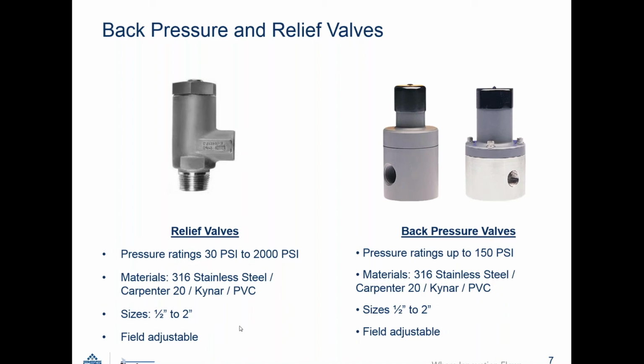Back pressure valves are required generally when there's a pumping situation where it's going into a low pressure situation. Pumps generally need back pressure to operate properly, so back pressure valves are required. A back pressure valve is just a device that restricts the flow coming through the valve to put back pressure against the pump. The materials we have in these are 316 stainless, Carpenter 20, Kynar, and PVC. Same size as 1/2 inch to 2 inches, and they're also field adjustable.